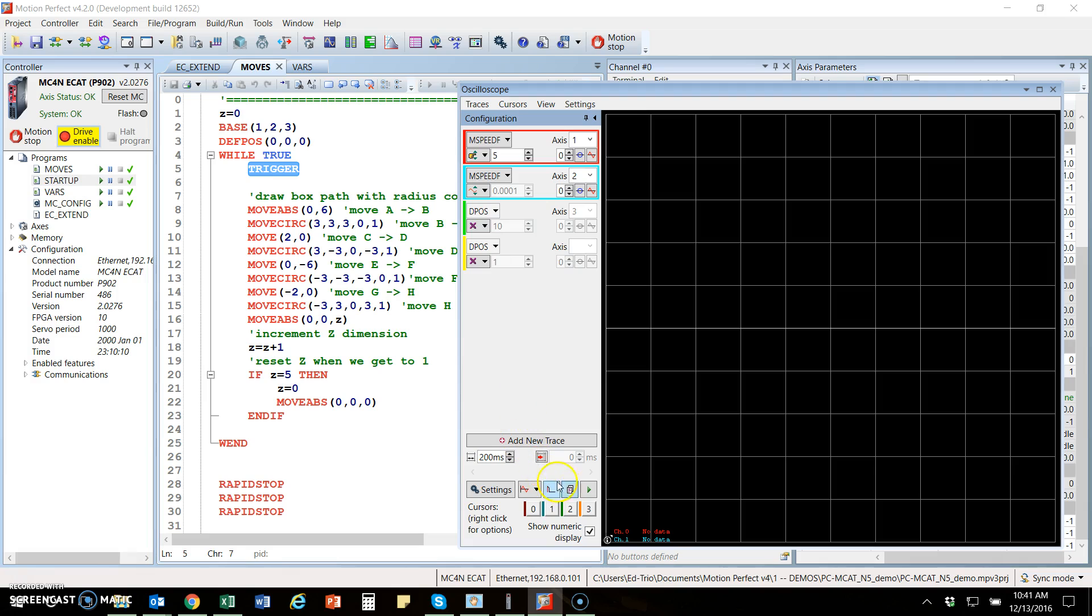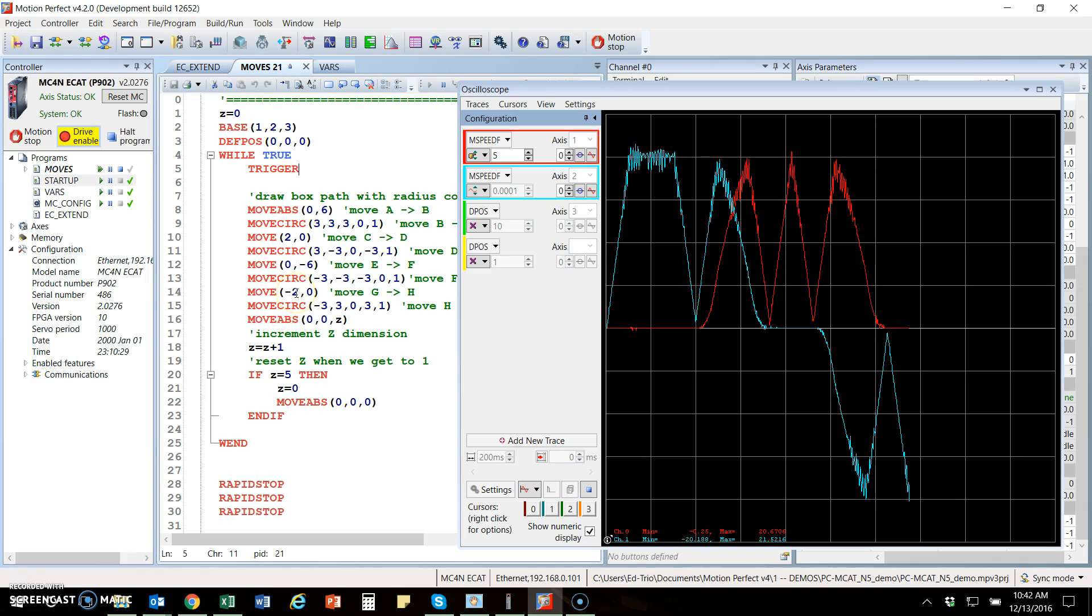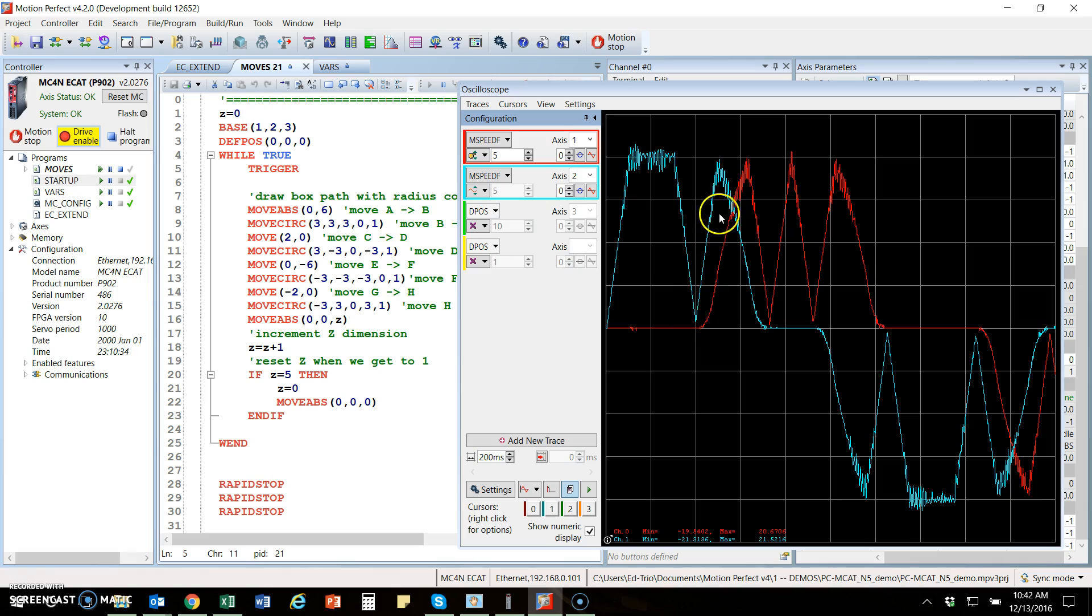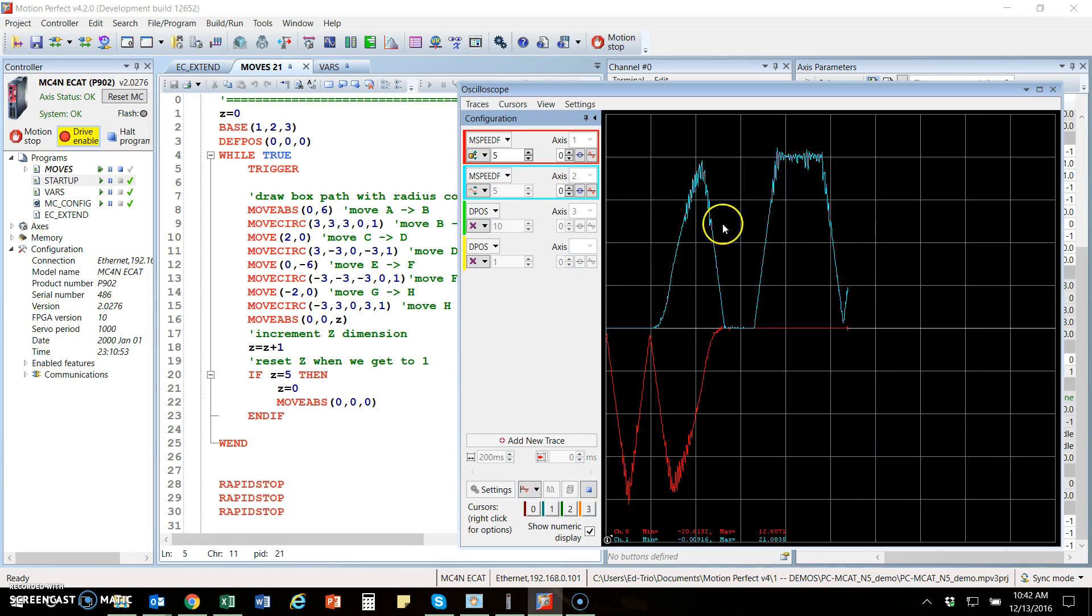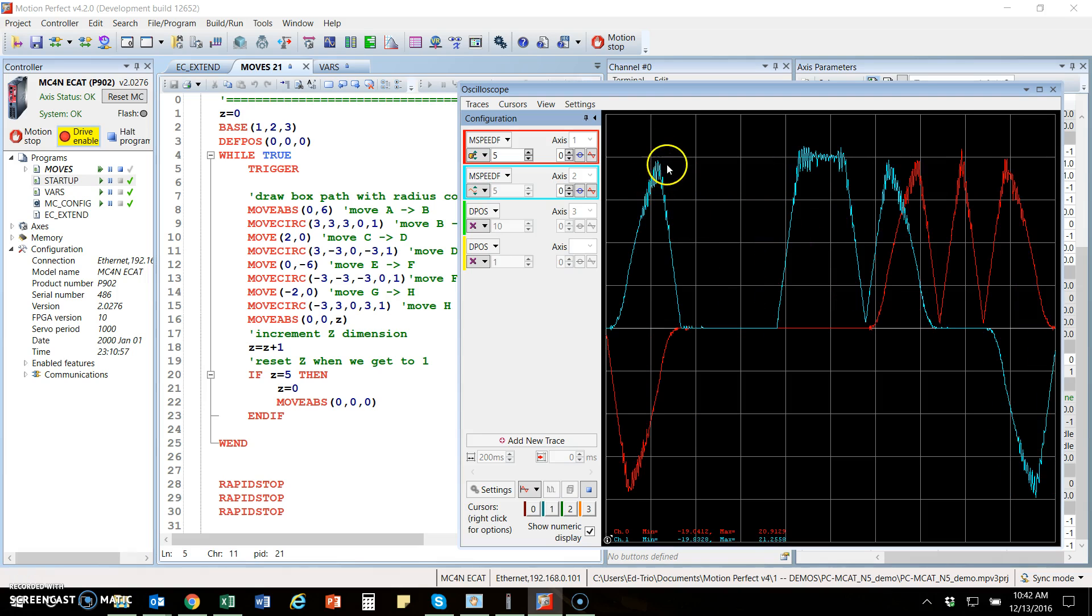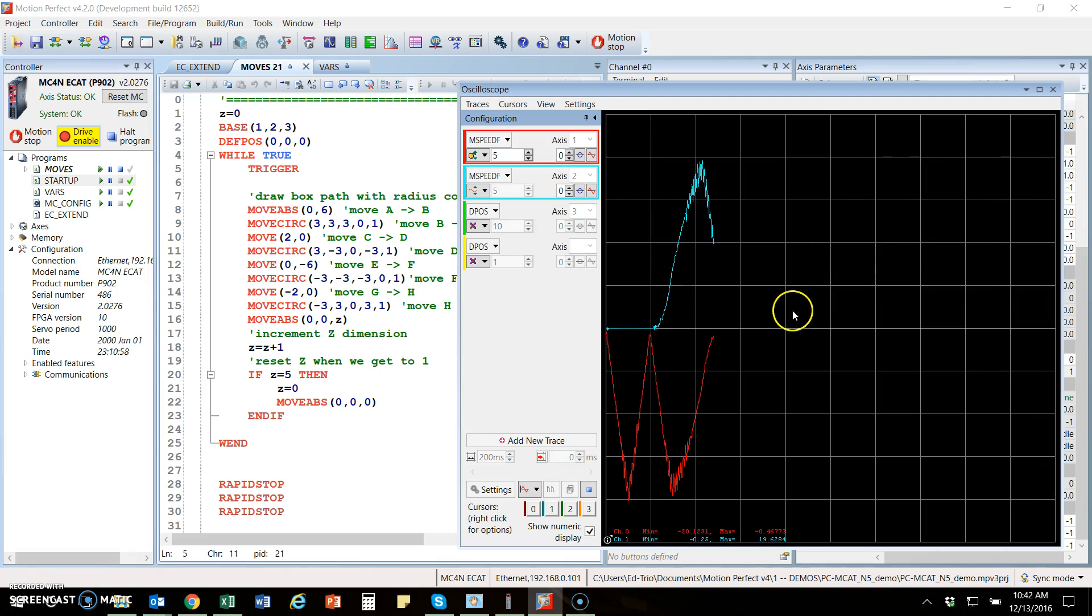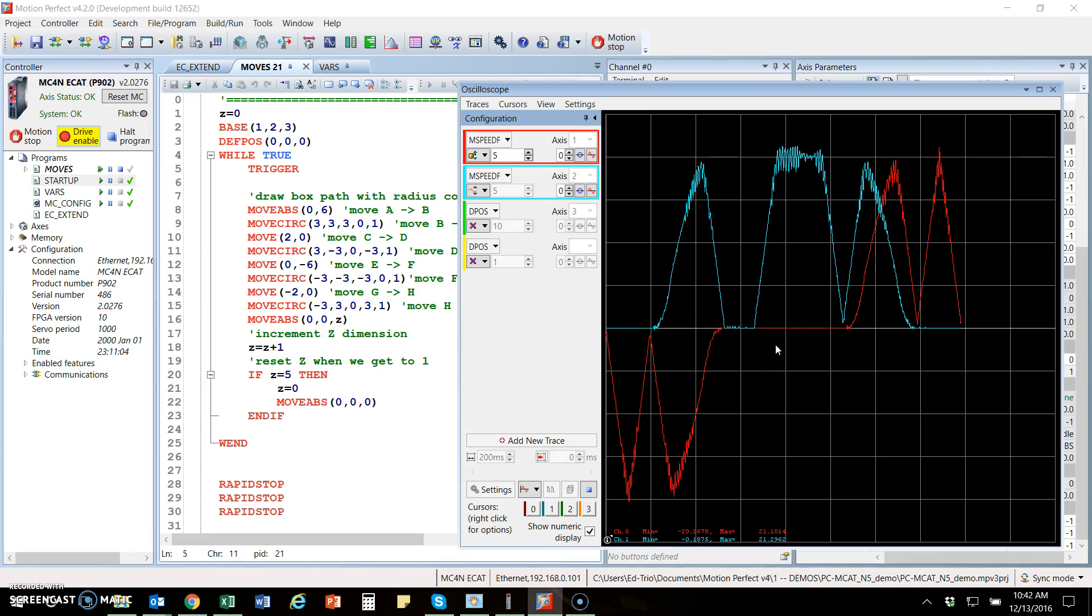Once you get that set up, it's a good idea to check your numerical values. You'll see your min and max here. We set up our time base here for 200 milliseconds per division. I should be able to run my moves program, and it'll do one pass of a velocity profile for each motor. We're plotting the profile for that oval square shape. This would be the first pass to maybe do some tuning alterations. The noise you see here is from the sampling, because this is some EtherCAT axes.